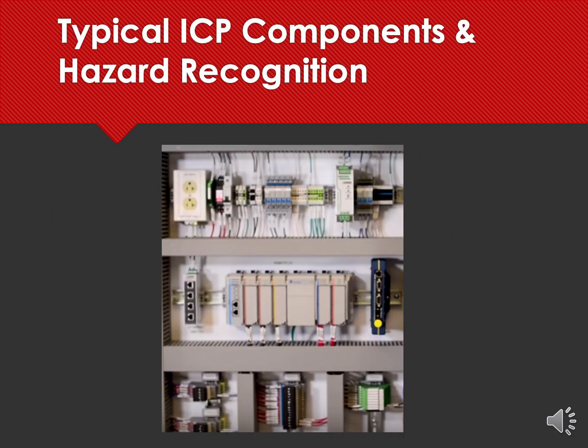What we see in front of you is an example of an industrial control panel. Let's be clear, there are literally hundreds of different configurations for industrial control panels. So this is by no means the standard by which we should measure them. This just happens to have a lot of the equipment we'll typically find on both the AC voltage side and the DC voltage side of the panel. And we'll go through each section of the panel and talk about the electrical hazards associated with each one.